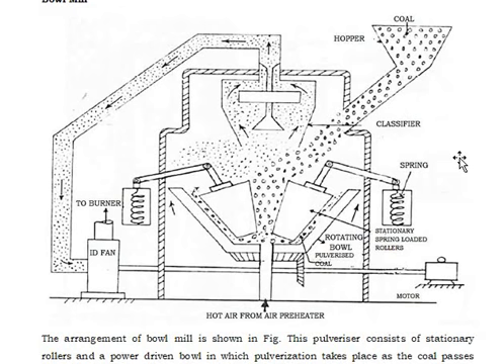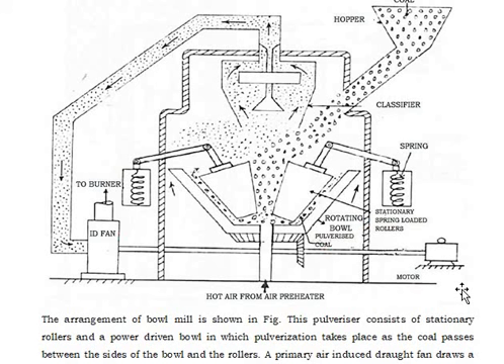Hot air from the air preheater enters where coal is fed from the hopper into the rotating bowl. You can see the rotating bowl in the sketch where very hot air from the air preheater is available. The arrangement of the bowl mill is shown in the figure. This pulverizer consists of stationary rollers — you can see them in the figure — and a power-driven bowl in which pulverization takes place as the coal passes between the sides of the bowl and the rollers.